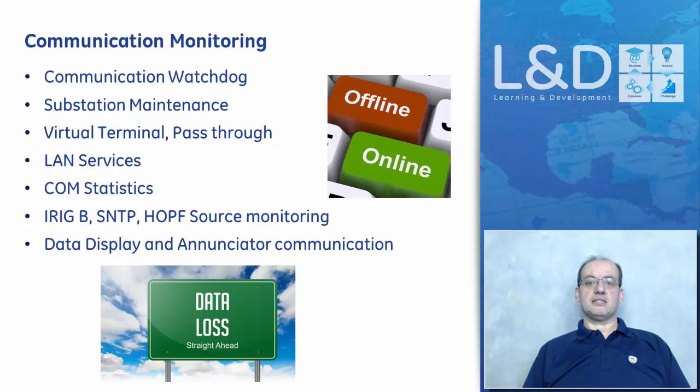Basically, the time device in the substation receives the time from the satellites and then distributes the time in the substation. How it distributes the time in the substation, there are many ways that it can do that. So it's either IRIG-B, which is one protocol for distributing the time over two wires all over the substation, simple network time protocol, or there are many other protocols that will allow you to receive the time from the satellite and then send the time.